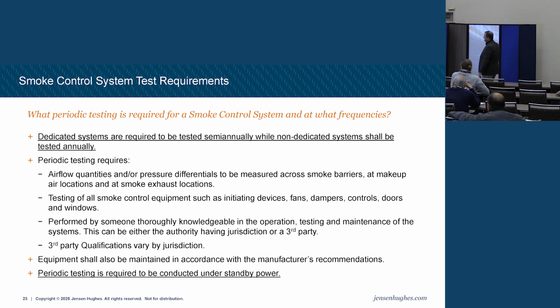Periodic testing is required to be conducted under standby power. So that may mean right there that you're doing this off hours, because you may have to drop power that inconveniences the rest of the building. So when we're doing full system testing, it is under battery backup or whatever the backup solution is.